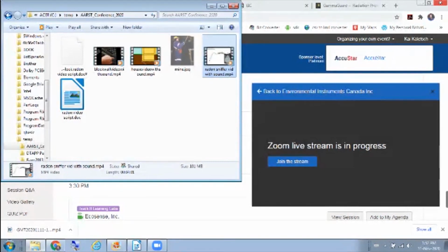It's not intended for legal measurements like real estate transactions and stuff like that. It's just to help you do the mitigation. So we don't really worry too much about absolute accuracy and traceability, it's going to be accurate to within plus or minus 10-20%, but we're not too worried about traceability. Do you require some sort of periodic factory check, maybe every year or every 2 years?